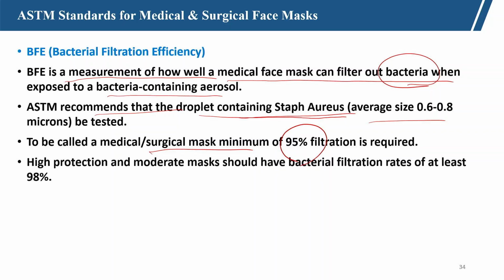To be called a medical or surgical mask, it must have more than or equal to 95% filtration efficiency; it should stop that much bacteria. If high protection is needed, then at least 98% efficiency should be there.